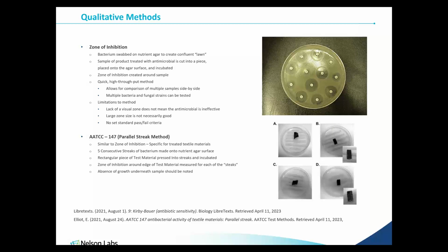This method can also be modified to allow for measurement of the durability of an antimicrobial coating over time. For example, samples can be transferred daily from one agar plate to fresh agar plates to see how long the antimicrobial activity is maintained or how many days a zone of clearing is observed. The method does have some limitations, however. The method does work best with flat pieces of product, and either plastics or textiles can be evaluated. The method does not distinguish between inhibitory activity, where the bacteria may still be viable within the zone of clearing, but cannot multiply and grow, and microbicidal or killing activity.